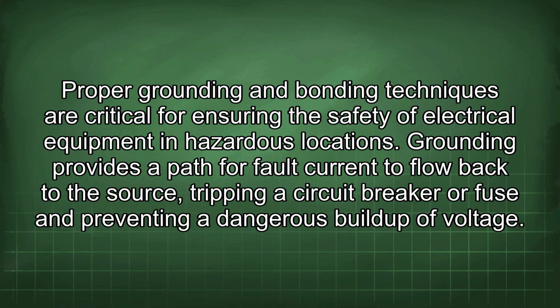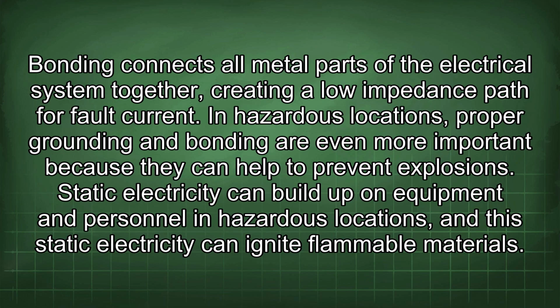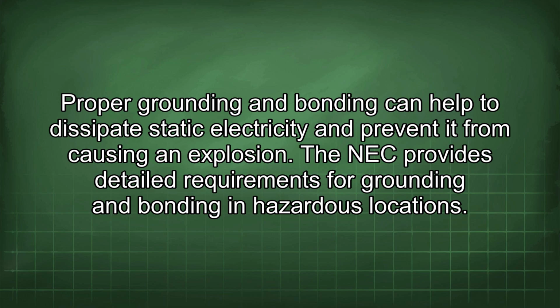Proper grounding and bonding techniques are critical for ensuring the safety of electrical equipment in hazardous locations. Grounding provides a path for fault current to flow back to the source, tripping a circuit breaker or fuse and preventing a dangerous buildup of voltage. Bonding connects all metal parts of the electrical system together, creating a low impedance path for fault current. In hazardous locations, proper grounding and bonding are even more important because they can help to prevent explosions. Static electricity can build up on equipment and personnel in hazardous locations, and this static electricity can ignite flammable materials. Proper grounding and bonding can help to dissipate static electricity and prevent it from causing an explosion.